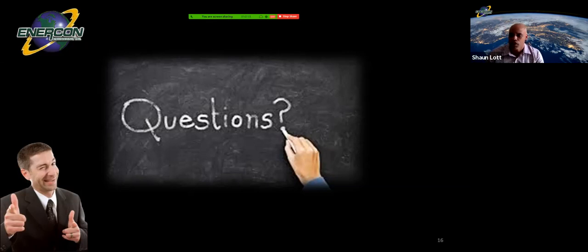Okay, our next question is dealing with time. When you add EMI protection, does it add any time to the development or the project build cycle? It really can, yes. The majority of the added time in the project cycle would be some time up front, where you would have additional engineering time to set up and create your zoned way of setting up your structure. And then oftentimes procurement time for specialty EMI devices or specialty EMI products, such as the cables or the honeycomb screens we talked about, or those gaskets. All of those have a longer procurement time when it comes to getting them in-house to start your build. So it really can add time in those regards.